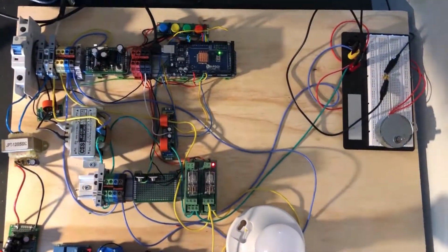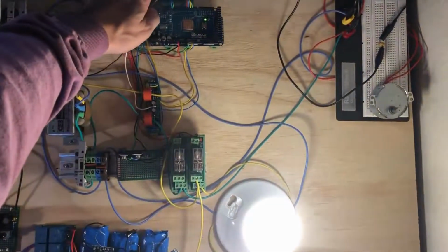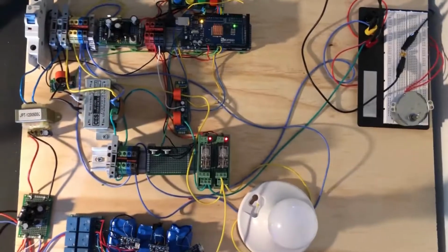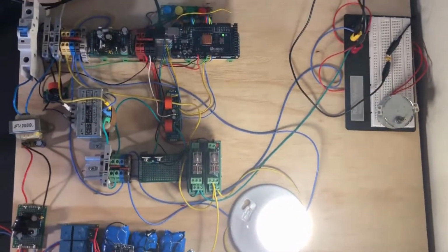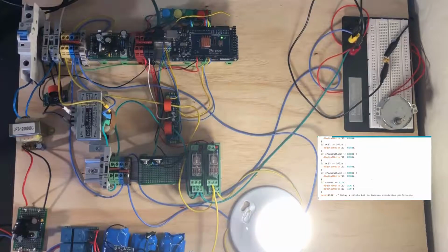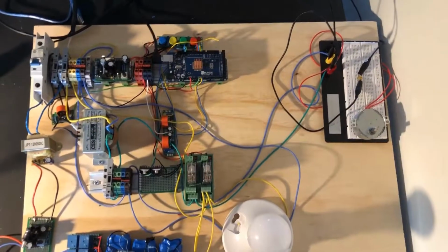Now I simulate fault 2, the residential load fault. The residential load power is disrupted. I reset the fault again, and then activate the critical fault 1. This kills power for the residential and the industrial loads. Now that I know my program is working and the controls are all intact, I can test the microgrid application with the inverter.